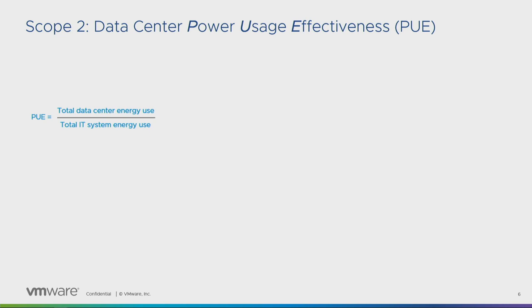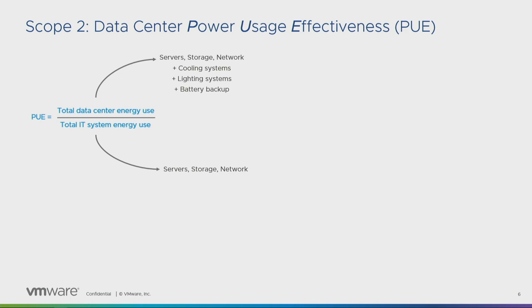It's power usage effectiveness. PUE is basically how efficient a data center is, and it's a very important metric. It's the total data center energy use—server, storage, network, plus cooling system, etc.—divided by what is used by the IT system.